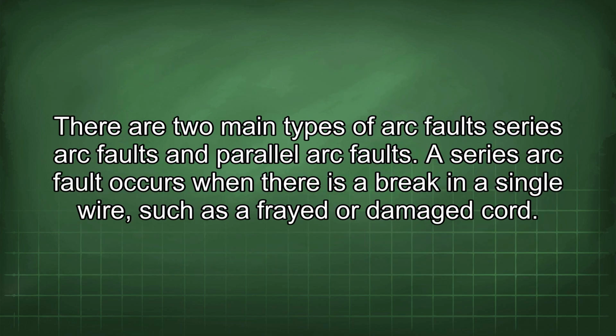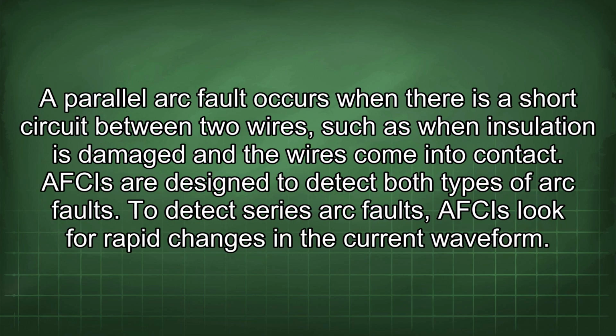There are two main types of arc faults: series arc faults and parallel arc faults. A series arc fault occurs when there is a break in a single wire, such as a frayed or damaged cord. A parallel arc fault occurs when there is a short circuit between two wires, such as when insulation is damaged and the wires come into contact. AFCIs are designed to detect both types of arc faults.